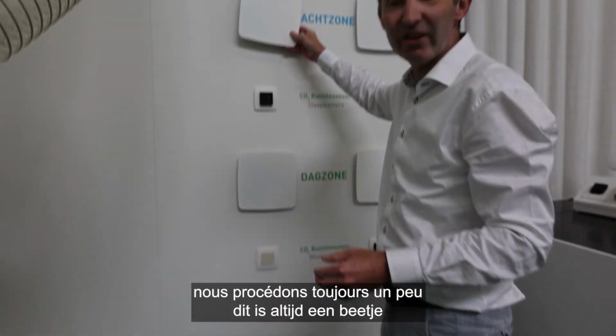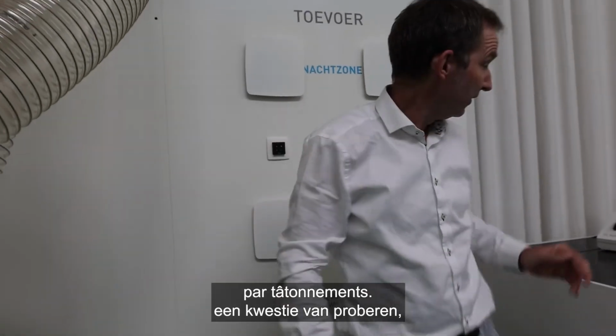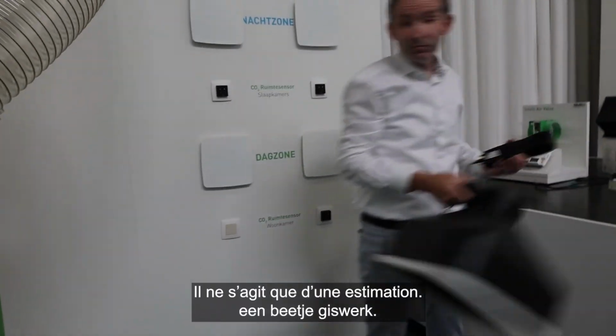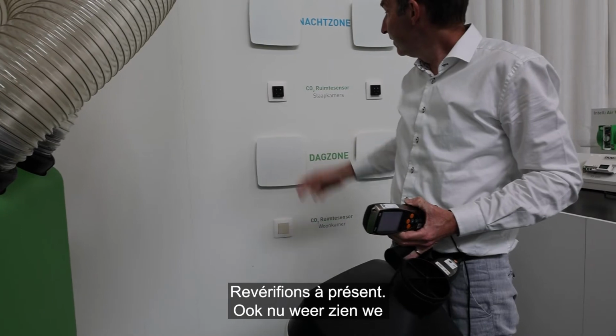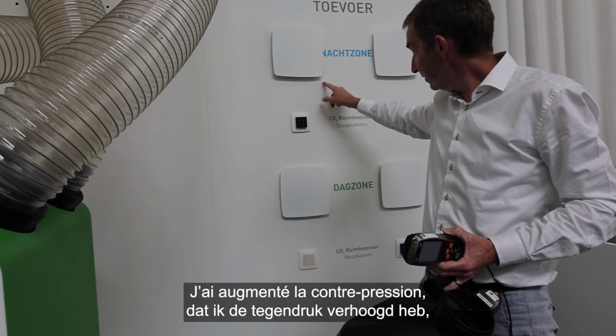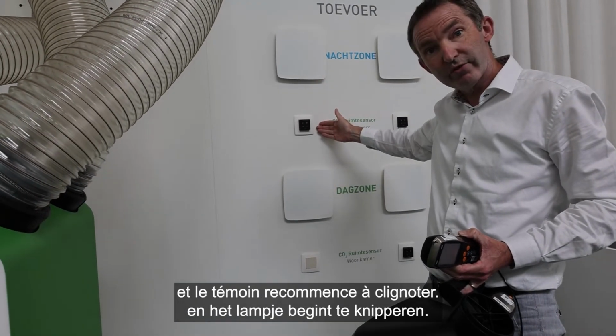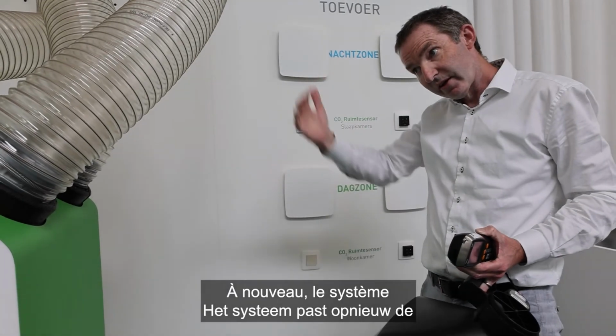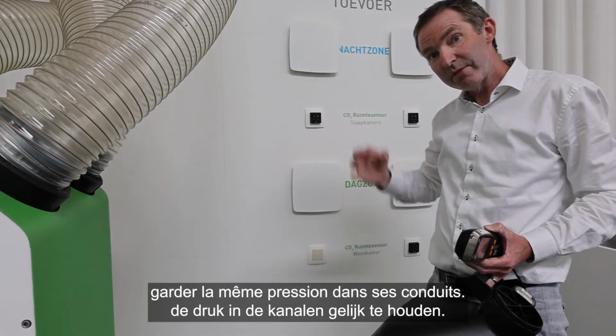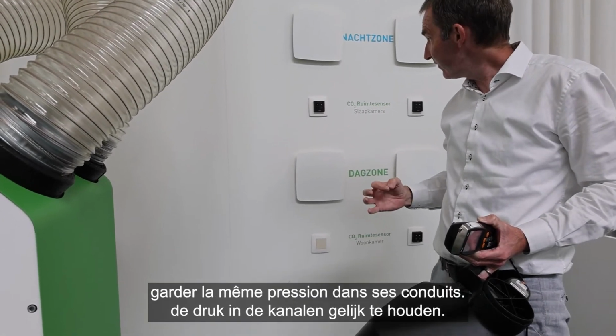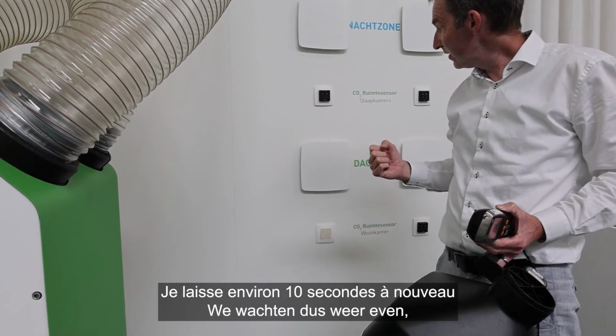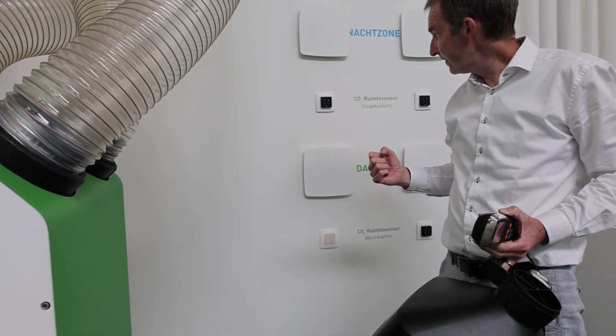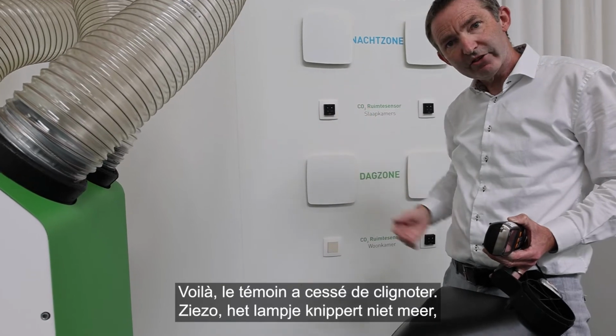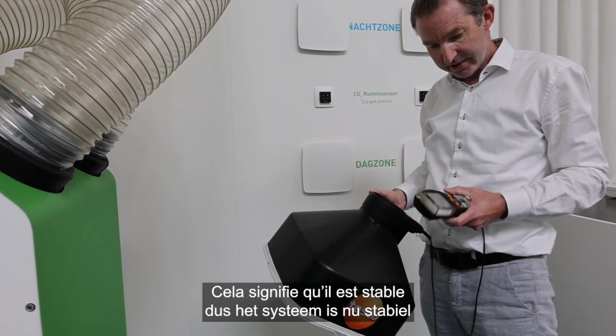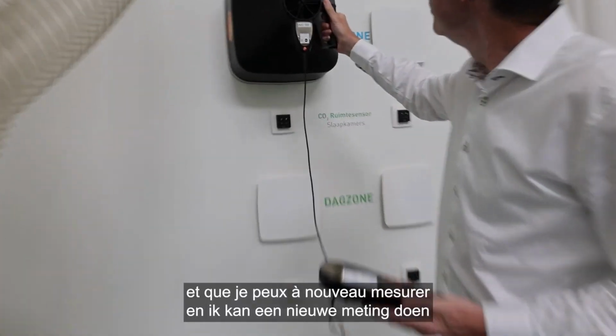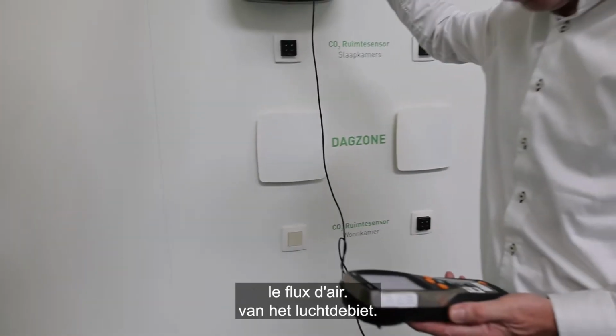This is obviously always a bit of trial and error, I'm just guessing now. You see I've increased the counter pressure again, so it starts flashing. The system is adapting its fan speed to keep the same pressure in the ducts. So I give it some time, approximately 10 seconds. There, the light has stopped flashing, meaning the system is stable and I can do a new measurement in terms of airflow.